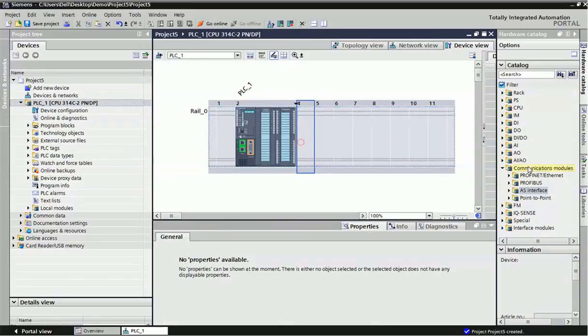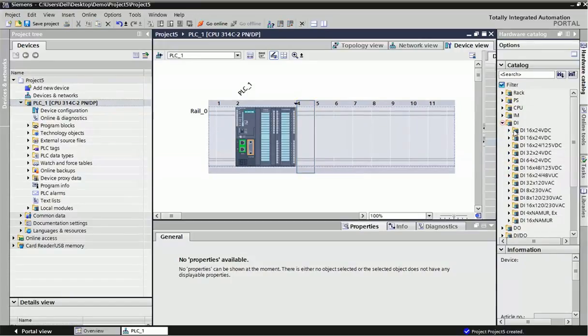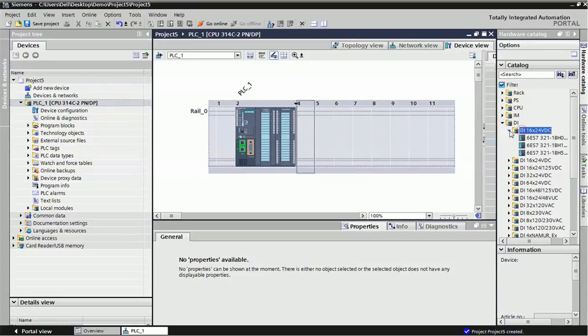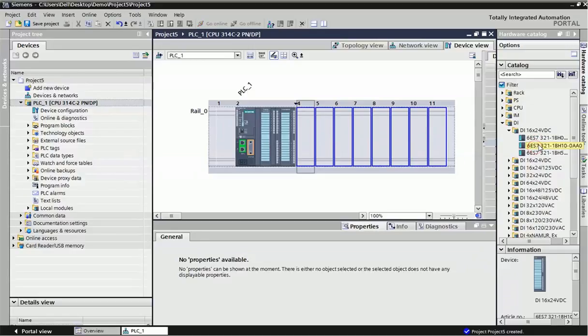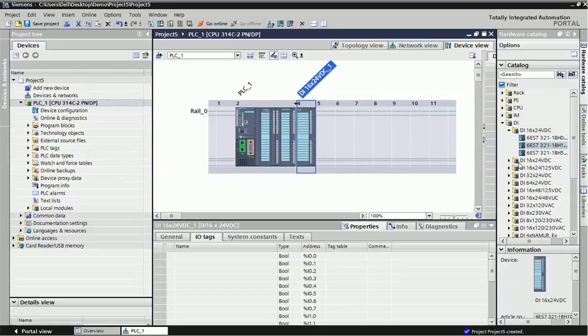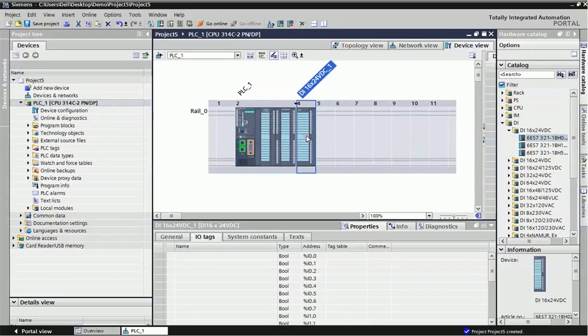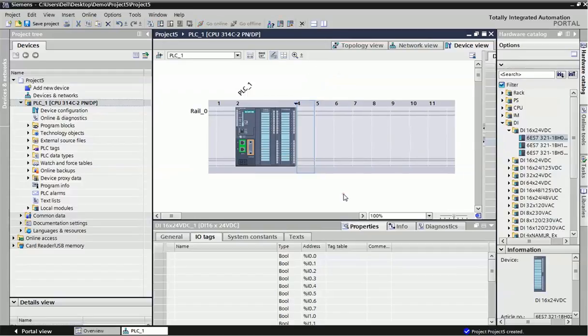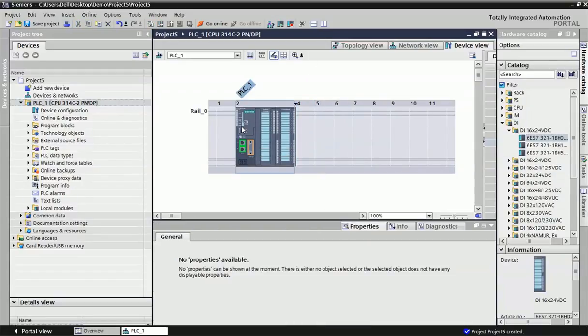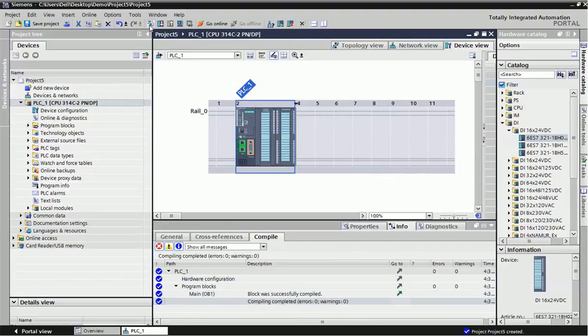If you want to add some modules, you can take from this hardware catalog. You just drag and drop like this, you just double click on that particular module. Right now I am assigning as is and then select the PLC. This is for compilation. Software compilation error and warning must be zero and then download this hardware into PLC.